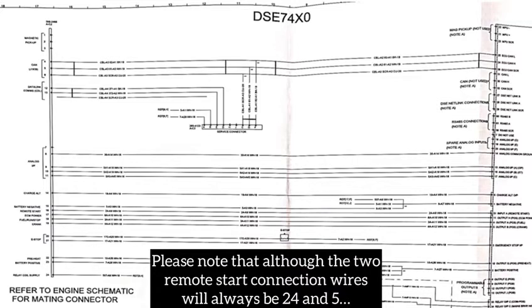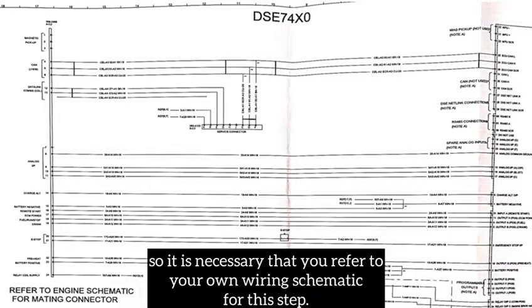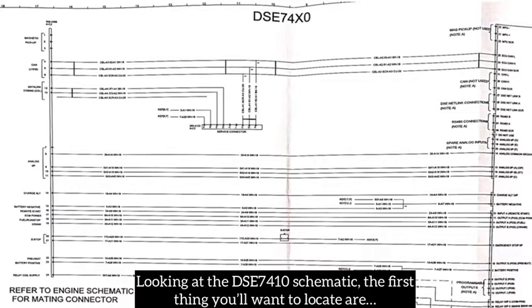Please note that although the two remote start connection wires will always be 24 and 5, the terminal block connections will vary based on your specific genset, so it is necessary that you refer to your own wiring schematic for this step.